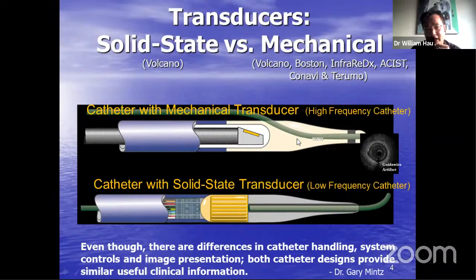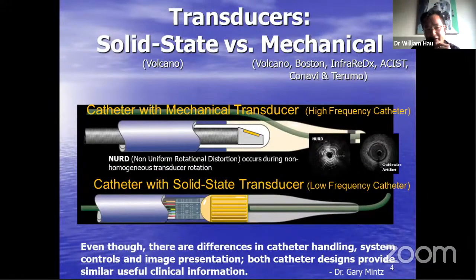And the other problem with this kind of IVUS catheter design is that the guide wire is outside the transducer. That's why we get a guide wire artifact when you do the IVUS pullback. And the other problem with this kind of catheter design is NURD. NURD stands for non-uniform rotational distortion. It occurs during non-homogeneous transducer rotation when the lesion is too tight or when the vessel is tortuous. It can happen.